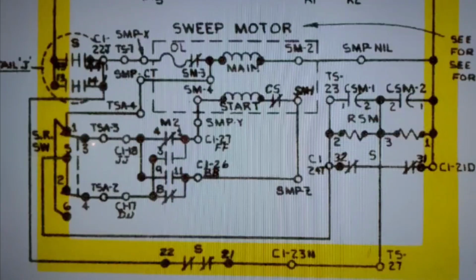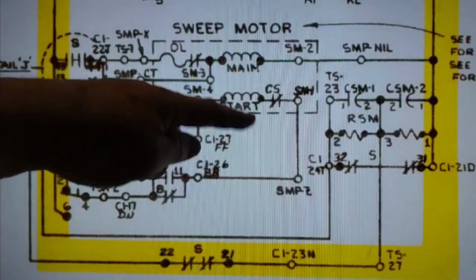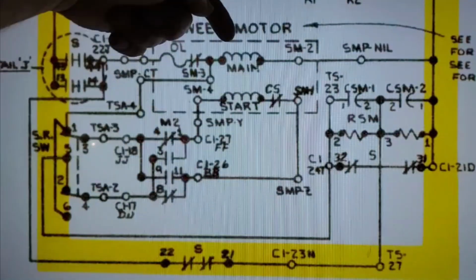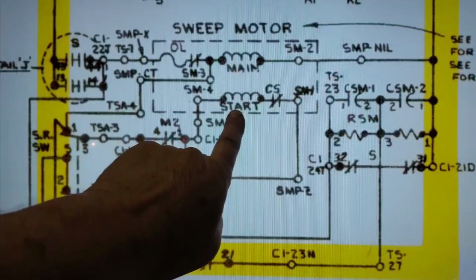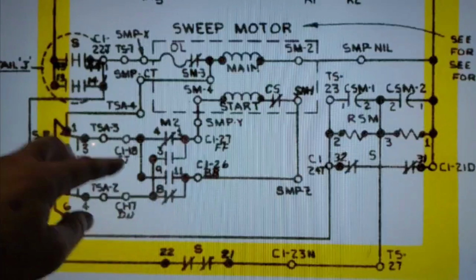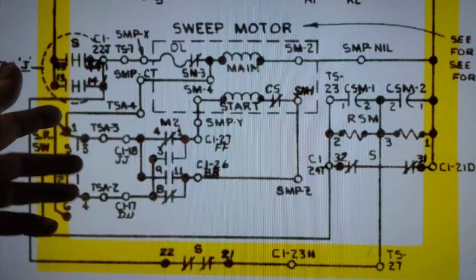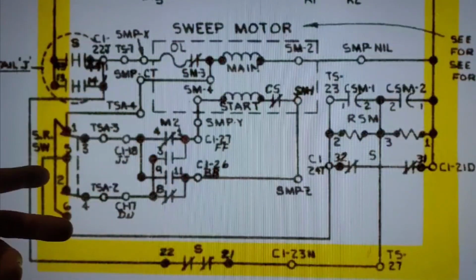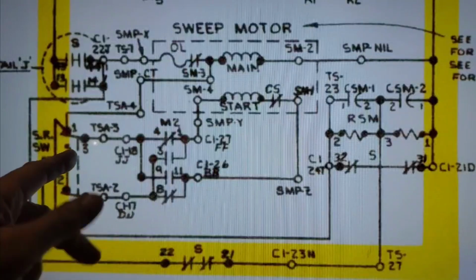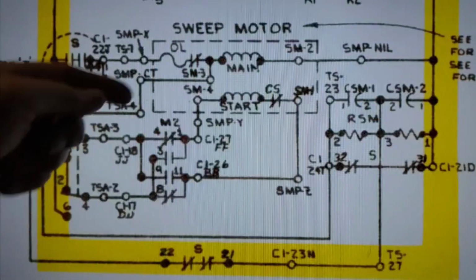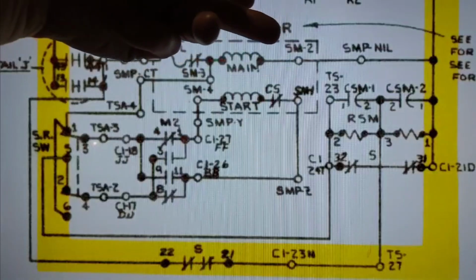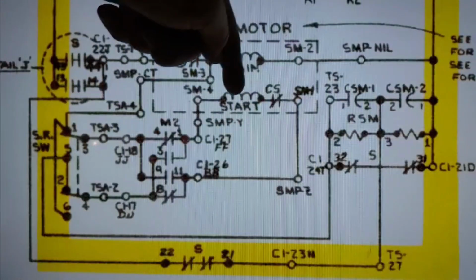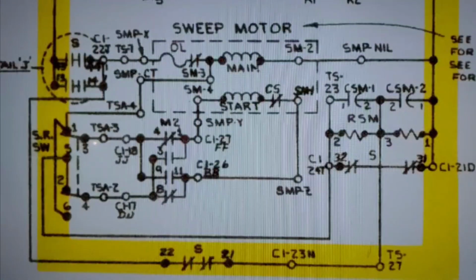Just we want to make sure that this circuit is running with a light. So we'll have an actual motor for the windings, but just a light for the start circuit to prove that this works. So running the sweep reverse for mine is just going to shut the light off, is all it will do, because I'm not hooking up the reverse. All it would do is relight the light, because the light doesn't care which polarity it is, it's still going to light up. But for the motor, it makes a difference which way it kicks it to get it going. So that's your sweep reverse circuit.